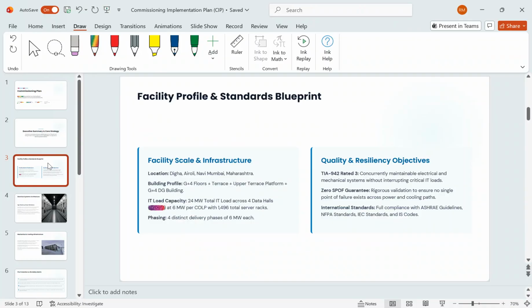The facility's quality and resiliency objectives are noted as TIA 942 rated 3. It means concurrently maintainable: maintenance can happen without interrupting the critical IT loads, without affecting the power load or the cooling load, the mechanical system, and the electrical load, meaning the critical IT loads. It should be rigorously validated to ensure no single point of failure exists across the power and the cooling path. It complies with international standards like ASHRAE guidelines, NFPA standards, IEC standards, and IS codes. So this is about the facility profile.